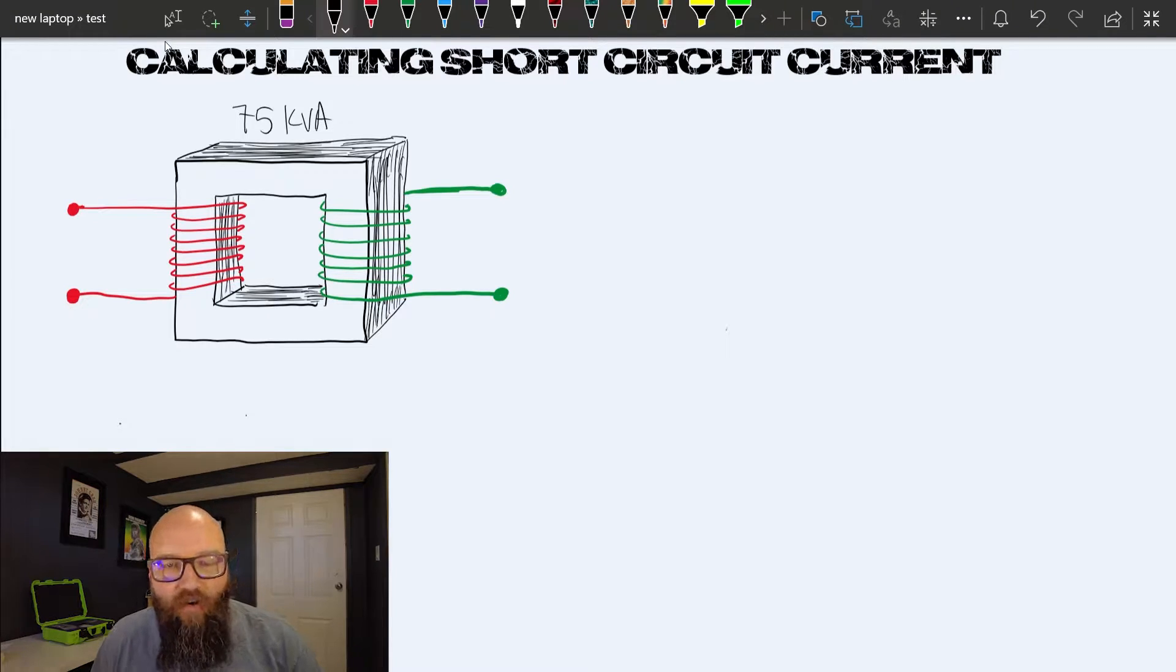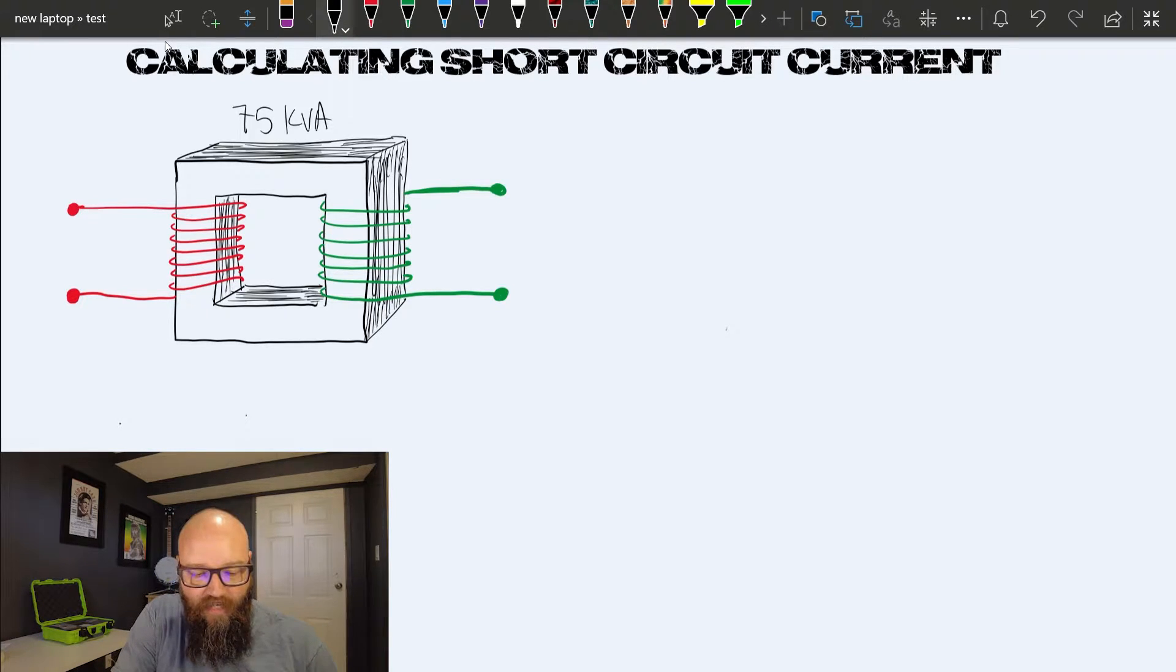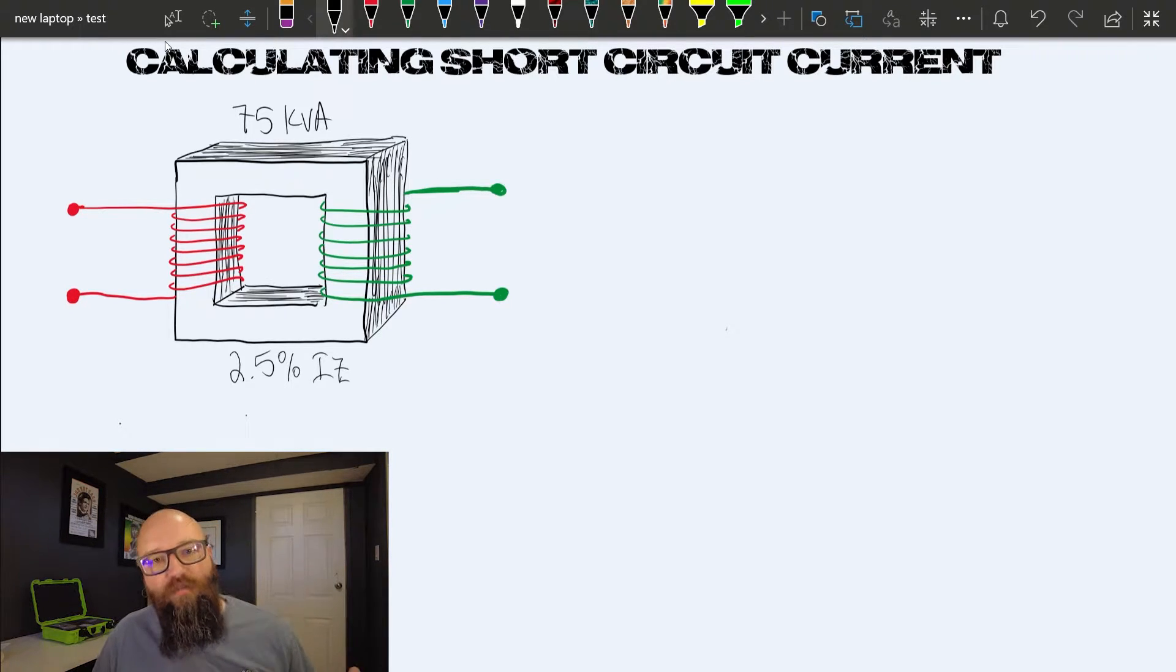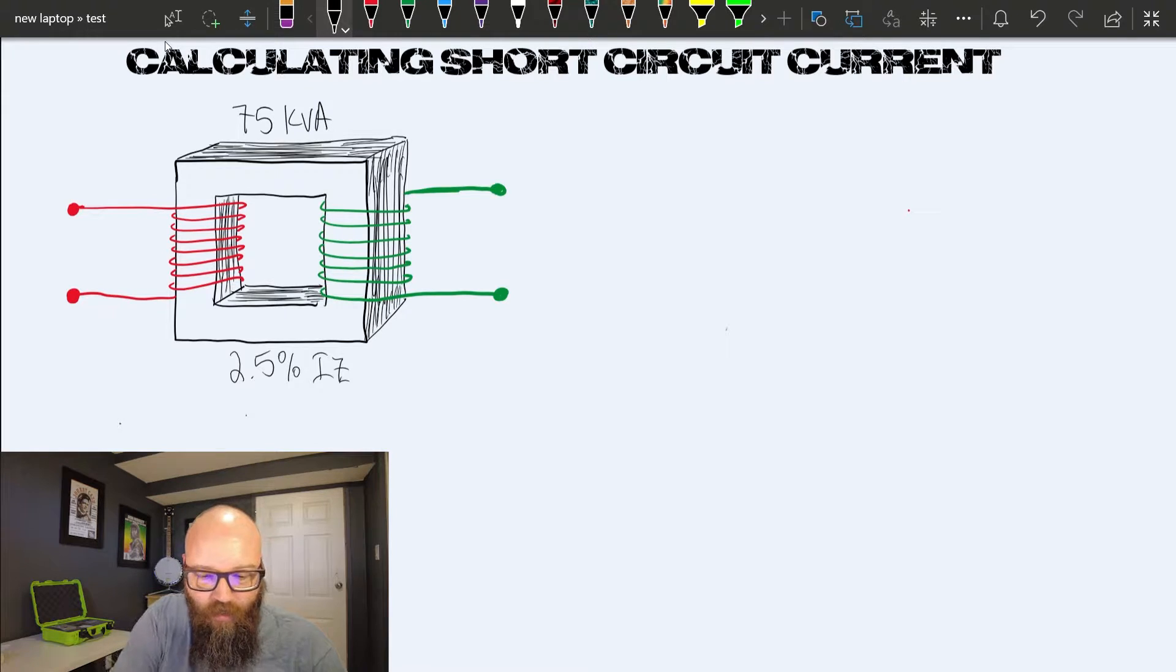If I was calculating the primary or secondary current on this transformer, I would simply use the 75,000 VA. We're going to say this transformer has a percent impedance of 2.5% IZ. These are the numbers I need to perform my short circuit current calculation. Before we do that though, we need some voltages. This is 600V on the primary stepped down to 120V on the secondary.